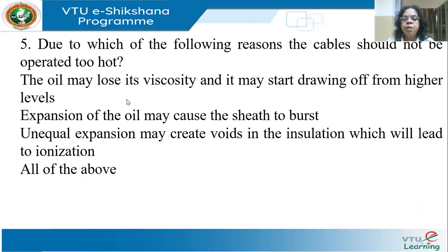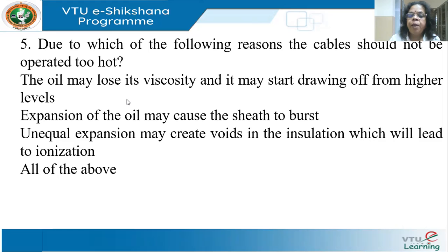For which reason should cables not be operated too hot? Oil may lose its viscosity and drain from higher levels; expansion of oil may cause the sheath to burst; unequal expansion may create voids in the insulation leading to ionization. All of the above can happen when the cable gets heated. Therefore it is imperative to provide suitable compensation when using cables to prevent excessive heat from damaging them.